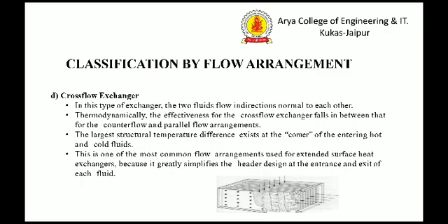Thermodynamically, the effectiveness of the cross flow exchanger falls in between that for the counter flow and parallel flow arrangement. The largest structural temperature difference exists at the corner of the entering hot and cold fluid. This is one of the most common flow arrangements used for extended surface heat exchanger.